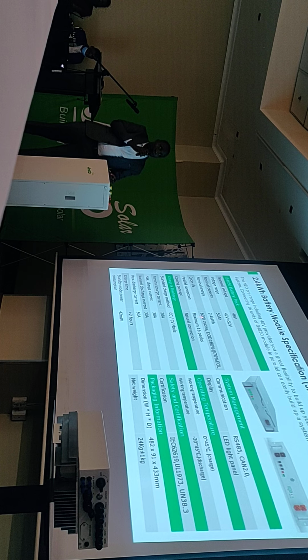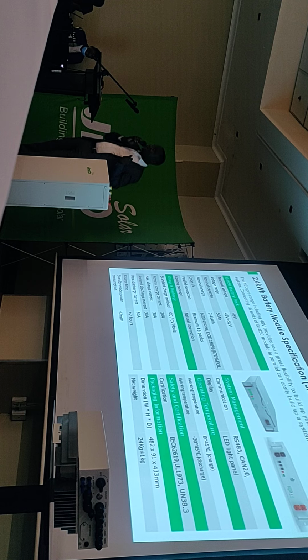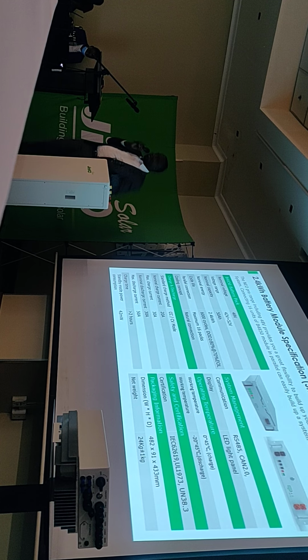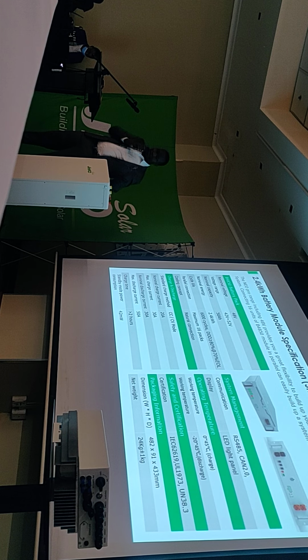And what is also very important is the number of cycles. The number of cycles is 6,000. So just to give you the reason why I mentioned that the batteries can last for 15 years: usually one charge and one discharge cycle per day, assuming 365 days in a year. So you do 6,000 divided by 365, and you'll get something more than 15 years. That's why we are saying the battery, depending on the application, will last for more than 15 years. And for the depth of discharge, for our solutions we can have more than 80%, even up to 95%.